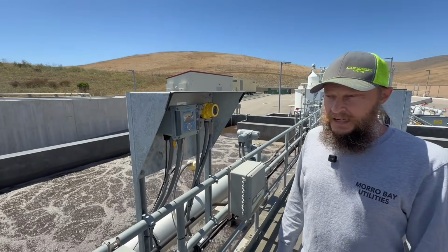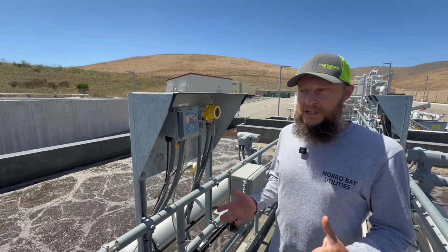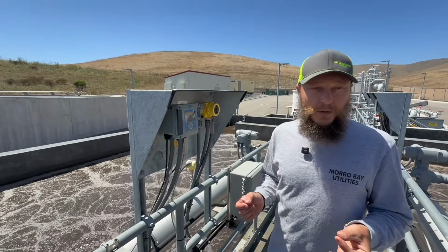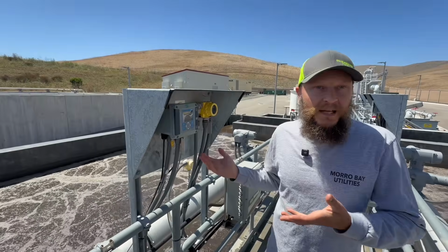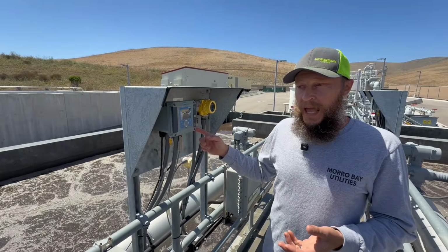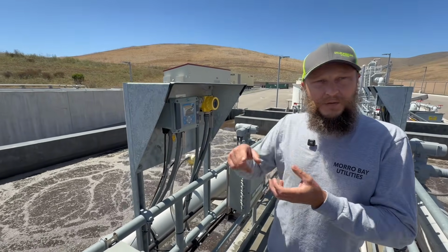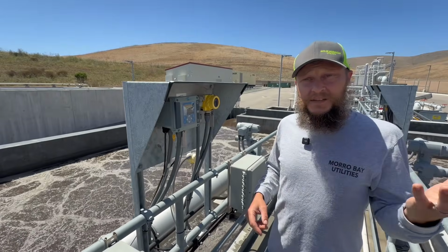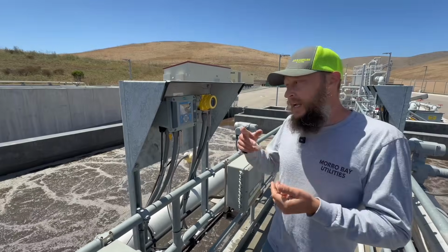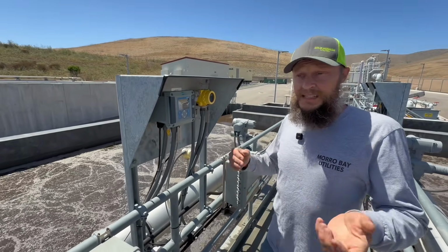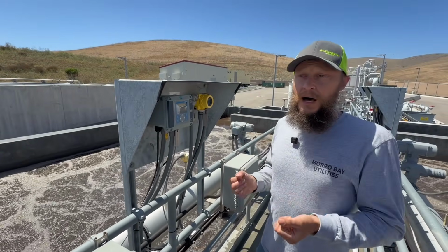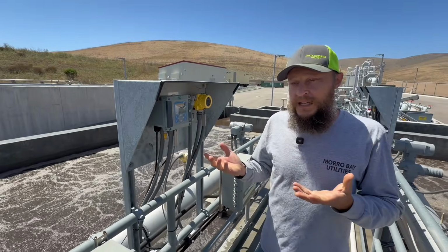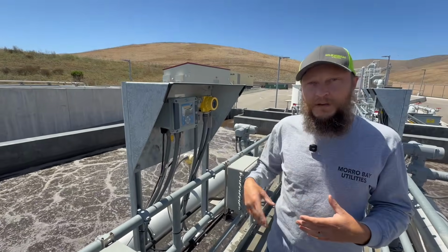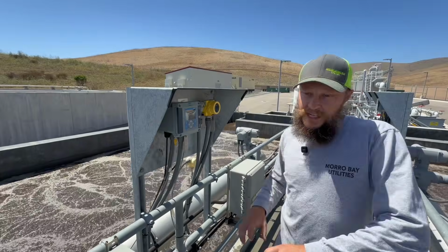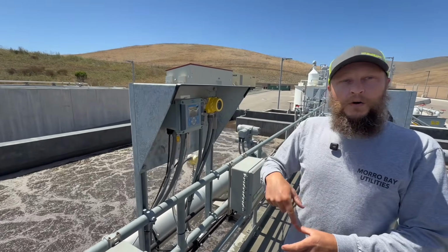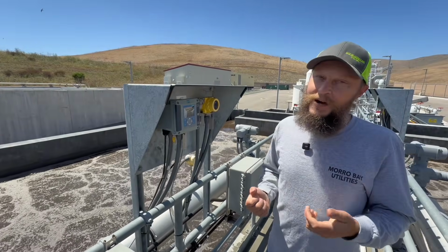A 4 to 20 milliamp signal is a type of signal that uses current and resistance to measure and share basically a number from one device to another. So this device is going to have a resistance in it that, when electricity is passing through it, will increase or decrease that resistance. And then on the other side, a PLC is interpreting what that resistance level is and turning it back into a number. So it's not a digital signal. It's actually the flow of electricity through the conductor. It's being restricted or opened. In the water world, it would be like interpreting what's happening with a flow meter, like how much volume is coming through into a number that you're reading from one side to another. Someone's got a hose and they're turning it up and you're watching that meter spin faster or slower, or even kinking that hose, right? And that's kind of how a 4 to 20 signal works.